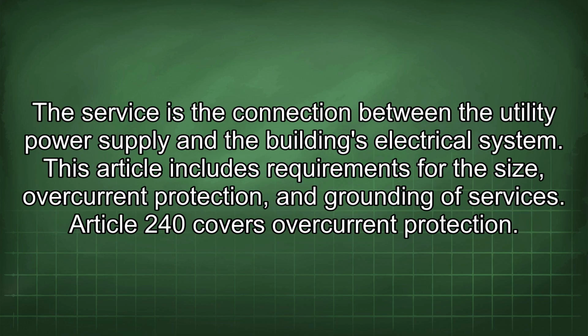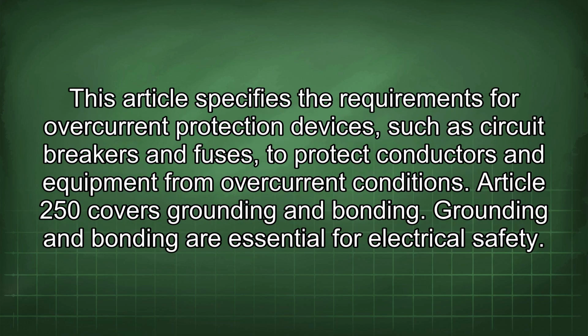The service is the connection between the utility power supply and the building's electrical system. This article includes requirements for the size, overcurrent protection, and grounding of services. Article 240 covers overcurrent protection. This article specifies the requirements for overcurrent protection devices, such as circuit breakers and fuses, to protect conductors and equipment from overcurrent conditions. Article 250 covers grounding and bonding.